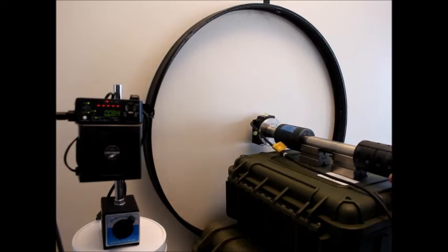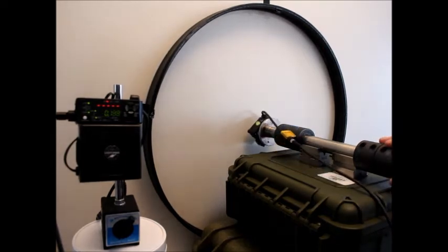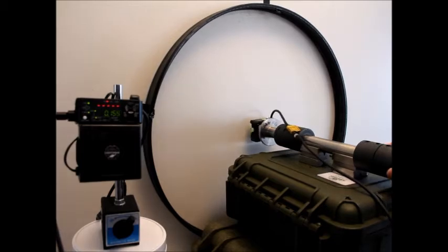Rotate the shaft to any point and the laser instantly measures the relative distance. From that we can find our max and min and determine the run out.